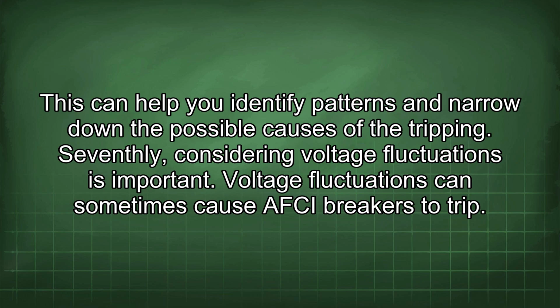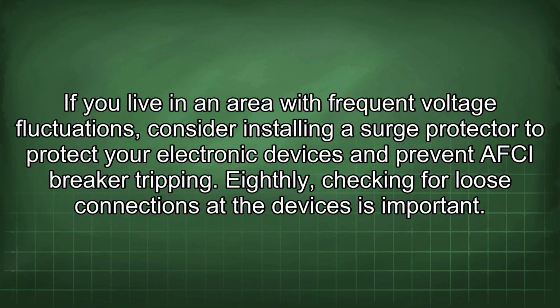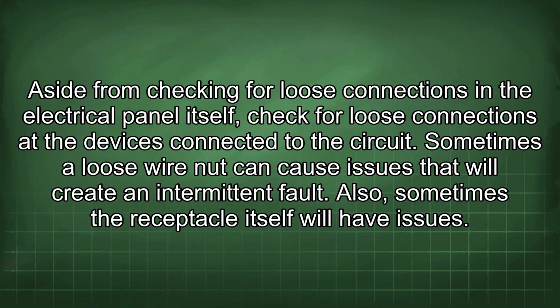Seventhly, considering voltage fluctuations is important. Voltage fluctuations can sometimes cause AFCI breakers to trip. If you live in an area with frequent voltage fluctuations, consider installing a surge protector to protect your electronic devices and prevent AFCI breaker tripping. Eighthly, checking for loose connections at the devices is important. Aside from checking for loose connections in the electrical panel itself, check for loose connections at the devices connected to the circuit. Sometimes a loose wire nut can cause issues that will create an intermittent fault. Also, sometimes the receptacle itself will have issues.